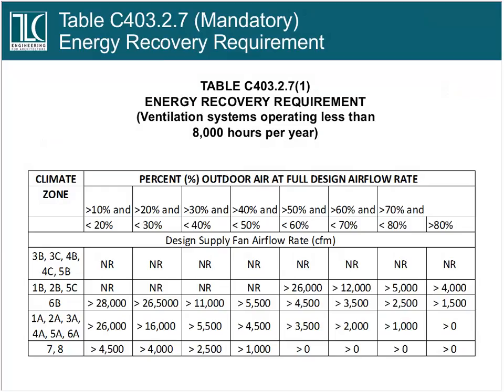There's another mandatory requirement now for energy recovery that divides on whether the building is operated 24/7 or not. It is pretty common to see air conditioning systems that have about 25% outside air at full supply demand, so that falls into this category here. If you're in the Gulf Coast area, 2A and 3A, and your air handling system has a supply flow of more than 16,000 CFM, then you're going to have to put energy recovery on that system. Now, a 16,000 CFM air handler is a box that's about 6 feet square. I mention this because this is going to have impact on mechanical room sizing.